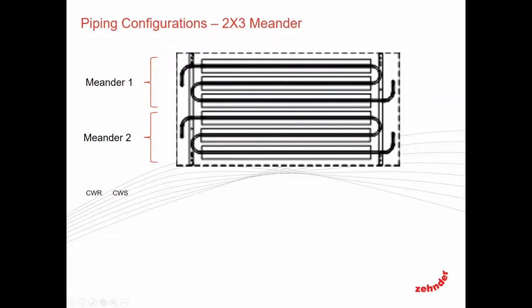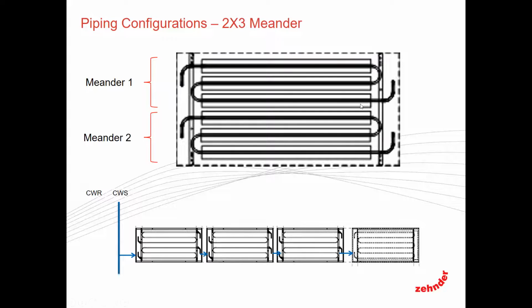Now, where this is important and where this is an advantage to the installer is because if you have a chilled water line going down a corridor, you can utilize 2x3 meander pipes all the way down one side in a single circuit, use a same end connection, and then return on that same corridor or hallway. So it gives you some flexibility, and it also minimizes the in-room piping or in-room zone piping that's going to occur. So there's a cost savings in utilizing these kind of circuits.